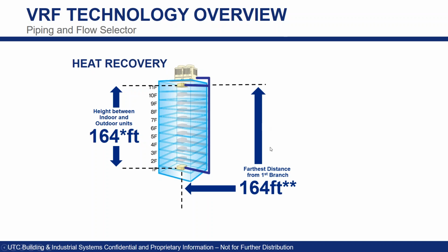So first and foremost, 164 feet. From our very first branch, and this branch is typically right below the cluster of condensing units, right below the deck, is going to be our first branch. So that's going to be our target mark. And then we're going to know that we'll be able to do 164 feet, obviously showing the elevation here, from that first branch or first takeoff from your main, leaving your outdoor units, all the way down to your furthest most indoor unit or fan coil.